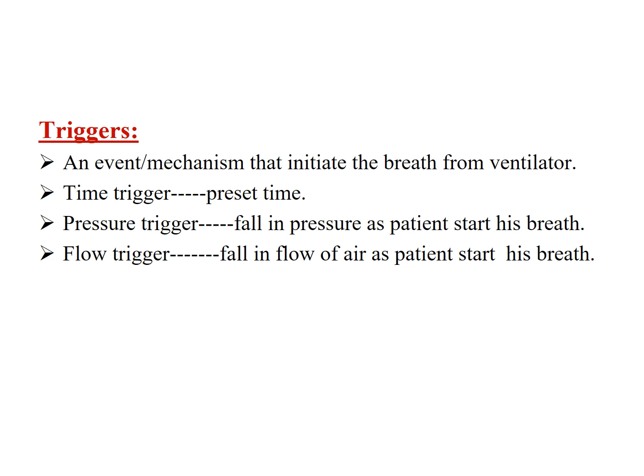Now the third one is the flow trigger, which again is regulated by the patient's own effort. Whenever a patient takes a breath, generates negative intrathoracic pressure, there is flow of air. This flow of air is detected by the transducers in the machine, which would do the same thing as with the pressure trigger. But the important thing here is that the transducers for flow trigger are much more sensitive compared to the pressure triggers. It is generally said, not a hard and fast rule, that for smaller kids, small neonates, those who are malnourished, for those whose ventilatory effort is weak, perhaps flow trigger is more appropriate if you want to keep them on trigger.